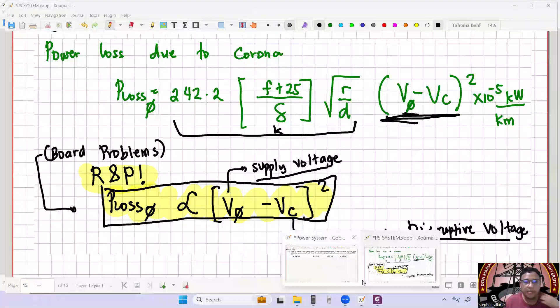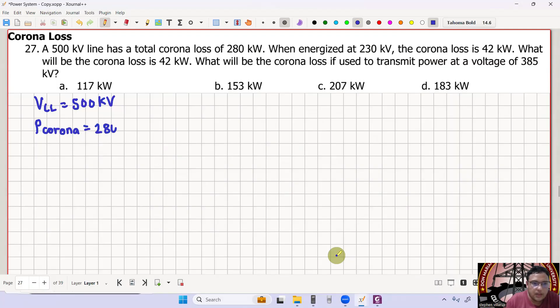So let's go to number 27. A 500 kilovolt line has a total corona loss of 280 kilowatts, so line-to-line voltage is 500 kilovolts. So P corona is 280 kilowatts. When energized at 230 kV, meron siyang condition number 2. So yung line-to-line voltage natin dito is 230 kV. The corona loss is 42 kilowatts. What will be the corona loss?